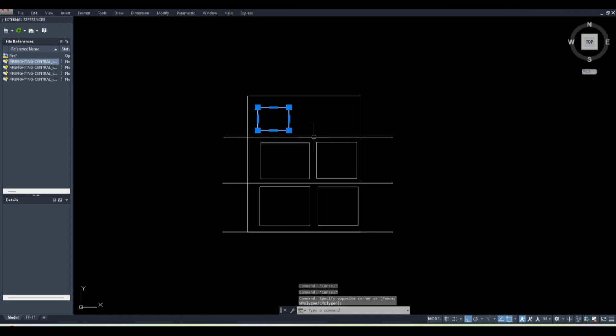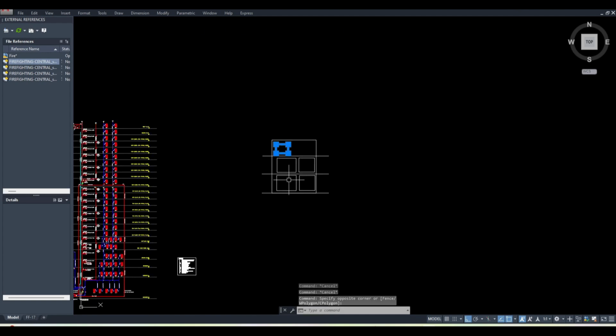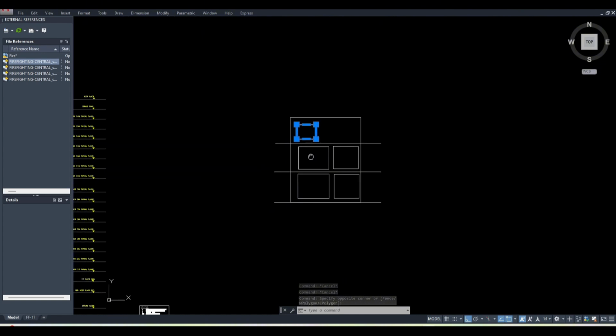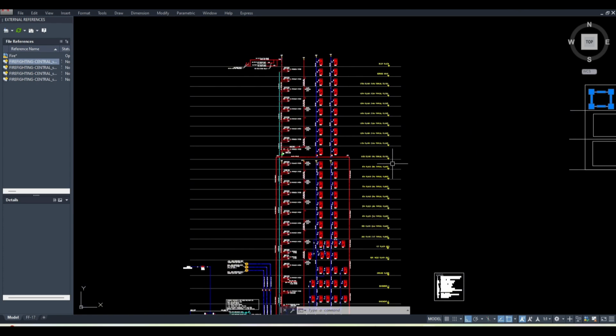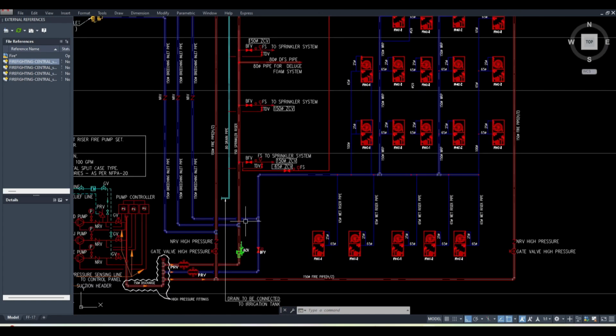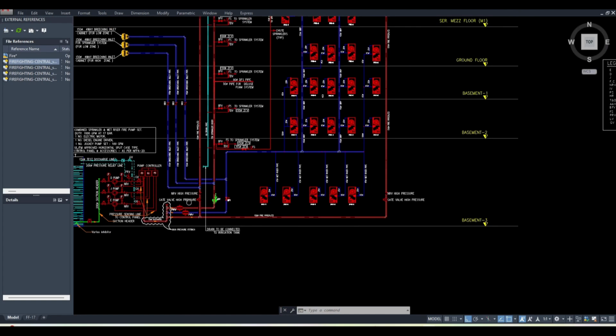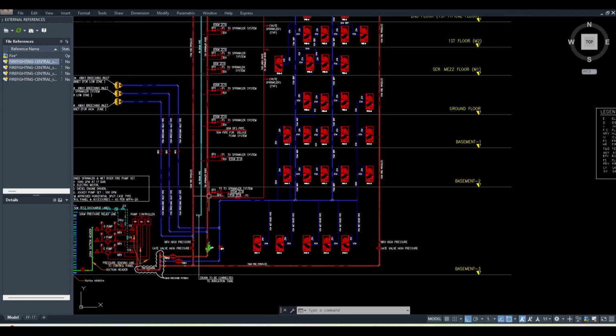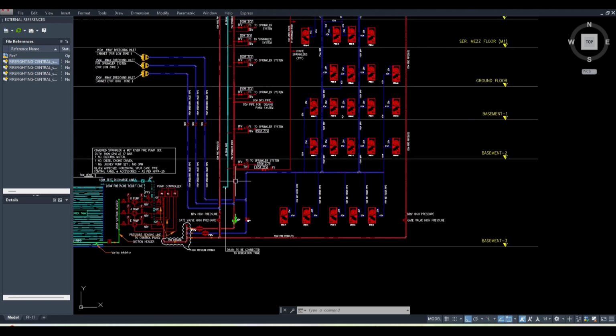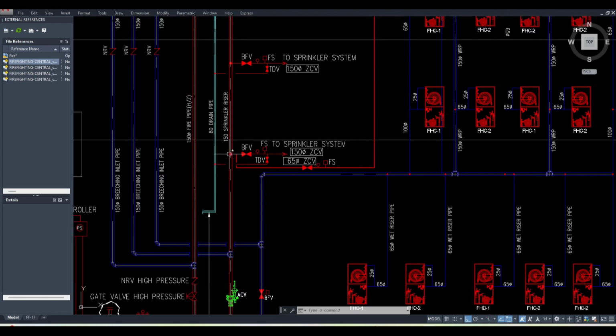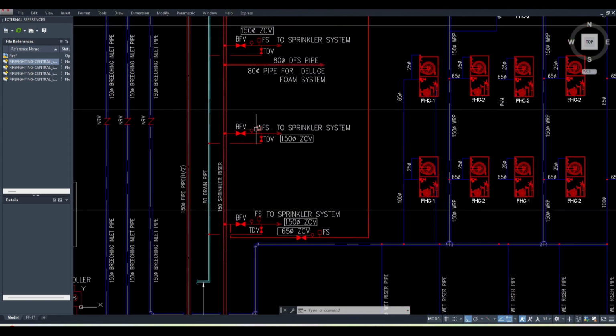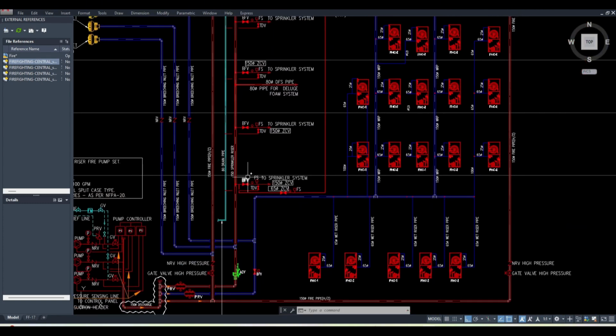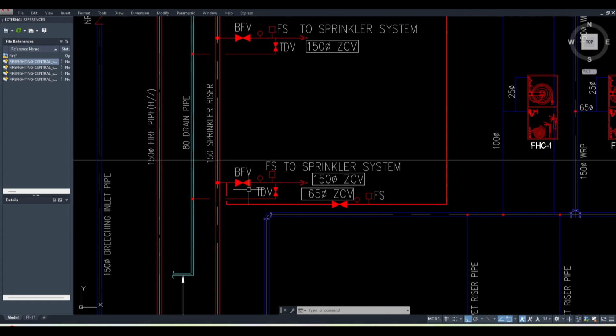Now why am I explaining you these things? Because each fire zone has to be served by a zone control valve. That is very important. So the fire riser which comes from the fire room goes in this direction. Now these two items I will explain later. So it serves one fire zone. So you see here, at every level one zone control valve is coming.